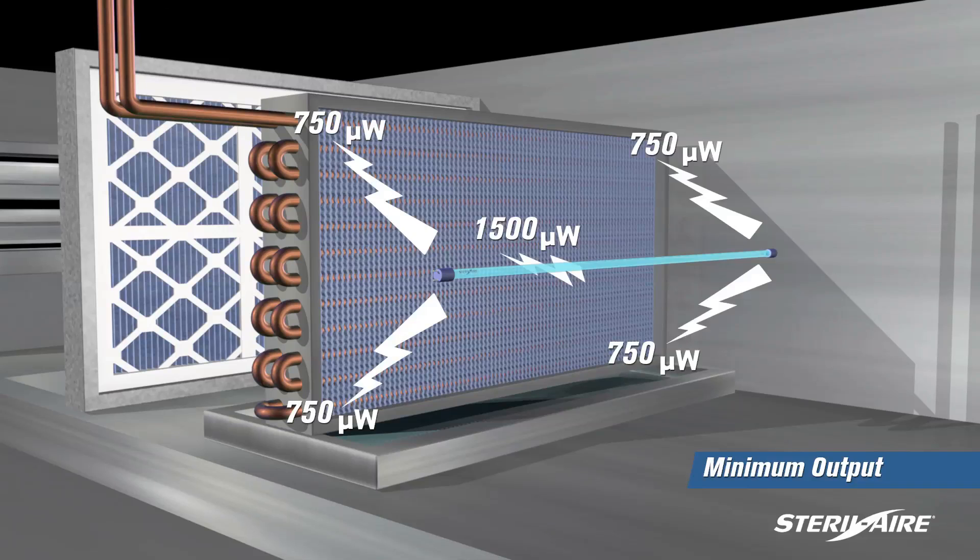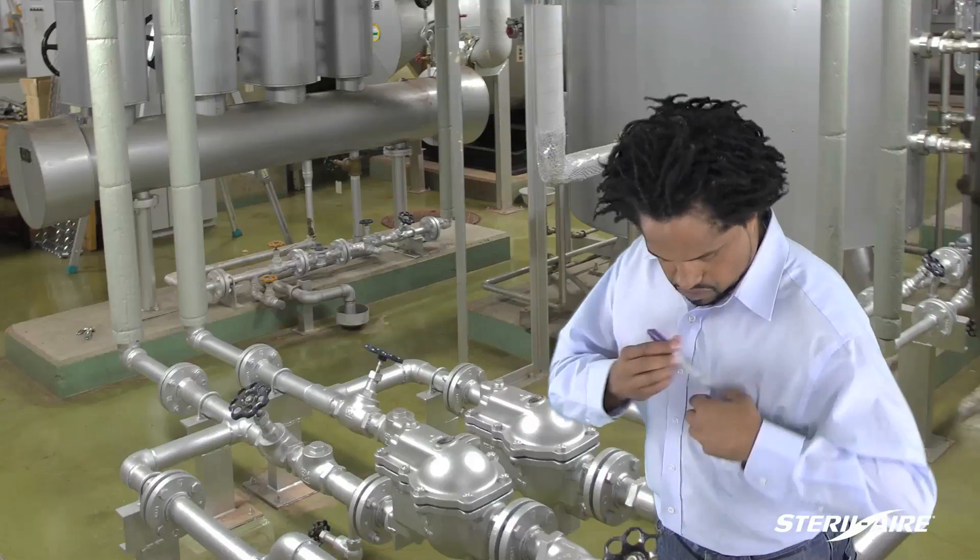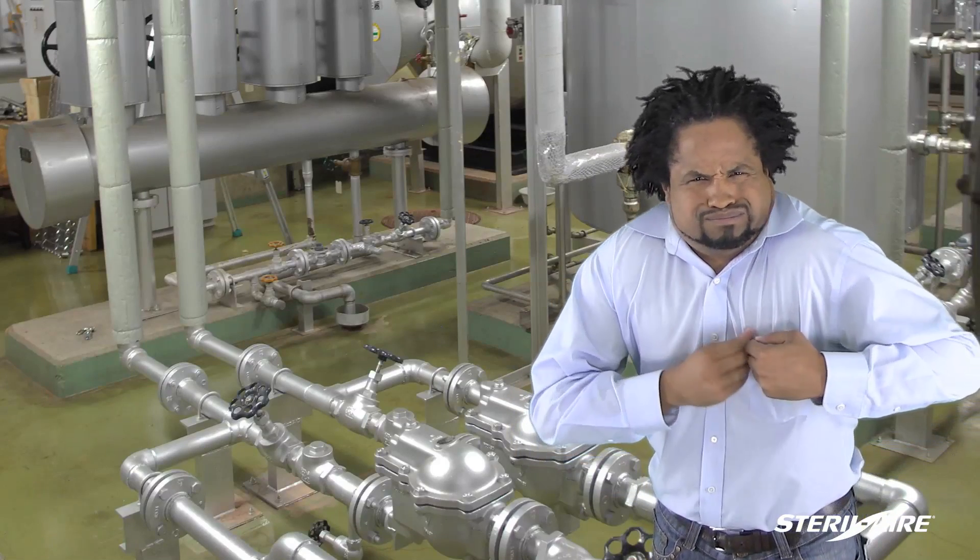In order to have sufficient microwatts to kill both the mold growing in the coil and the microbes in the air, Steril-Aire recommends at least 750 UVC microwatts at any point on the coil face. Without maintaining these standards, the people in the building will remain vulnerable.